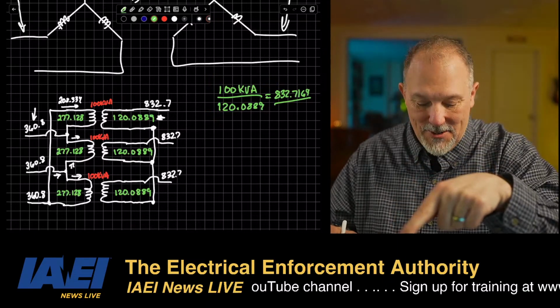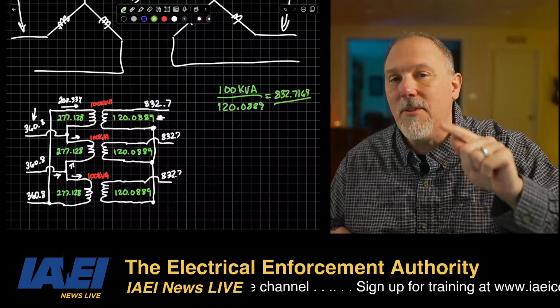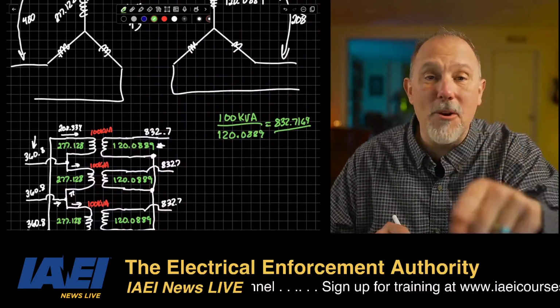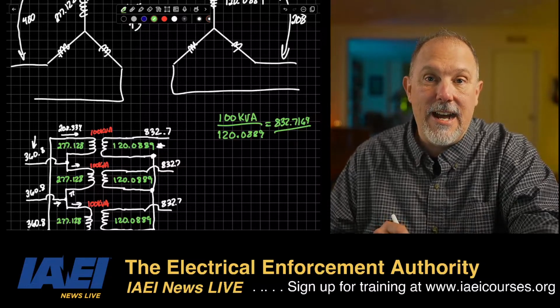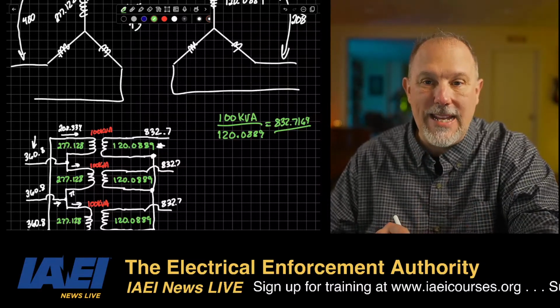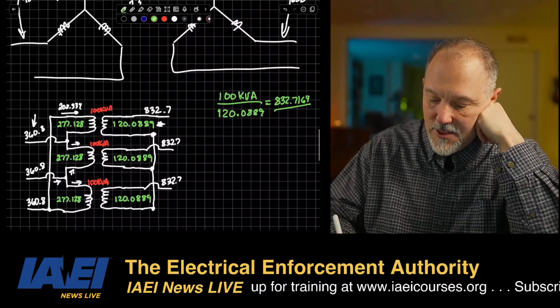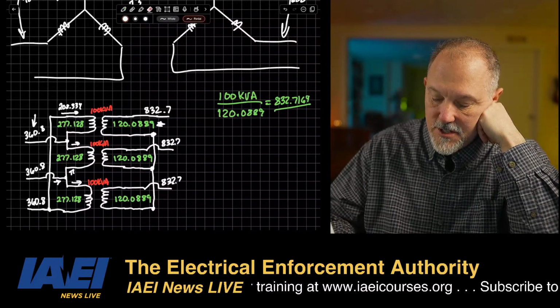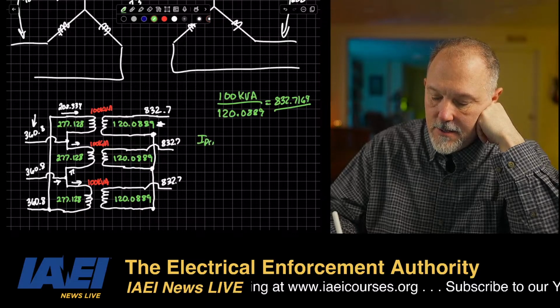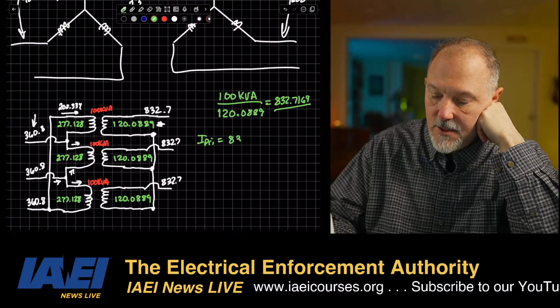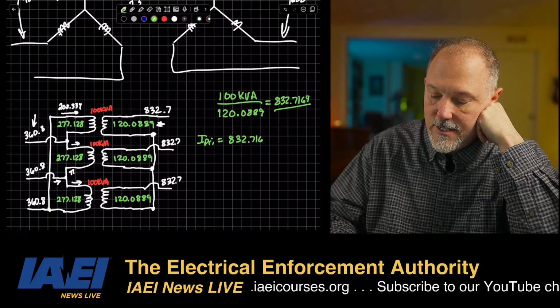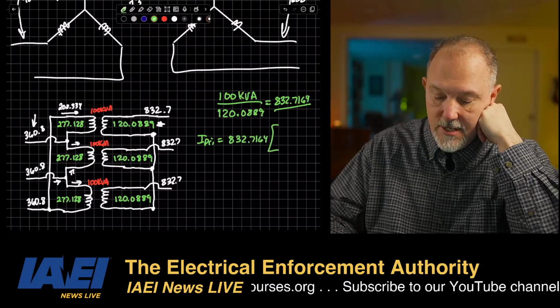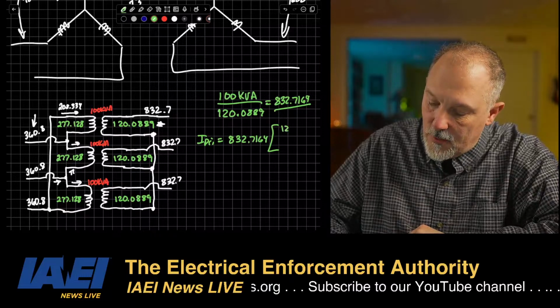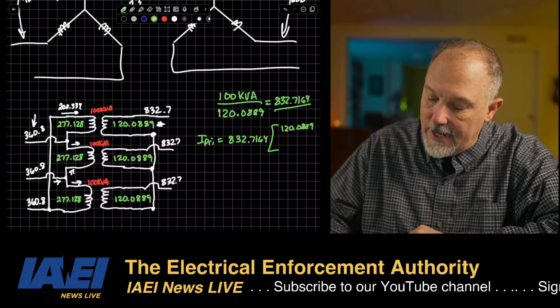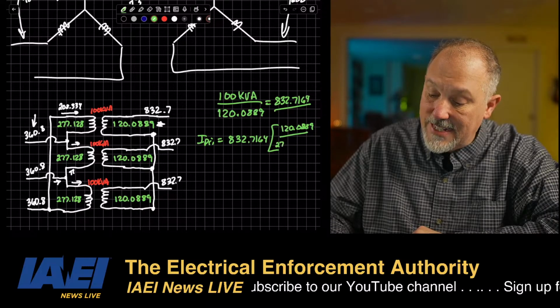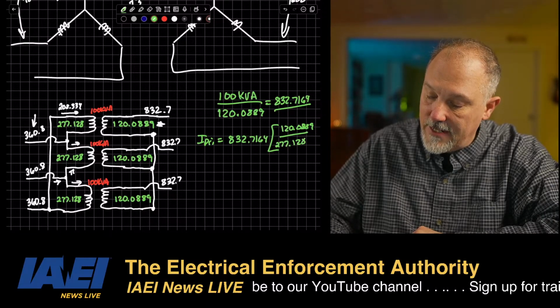Now I'm going to transpose it to the primary. But remember, I'm in Y. And I'm not working on 480 volts. I'm using 277.128. So if I want to reflect 832, I primary is equal to 832.7164 times the secondary voltage, 120.0889, divided by 277.128.